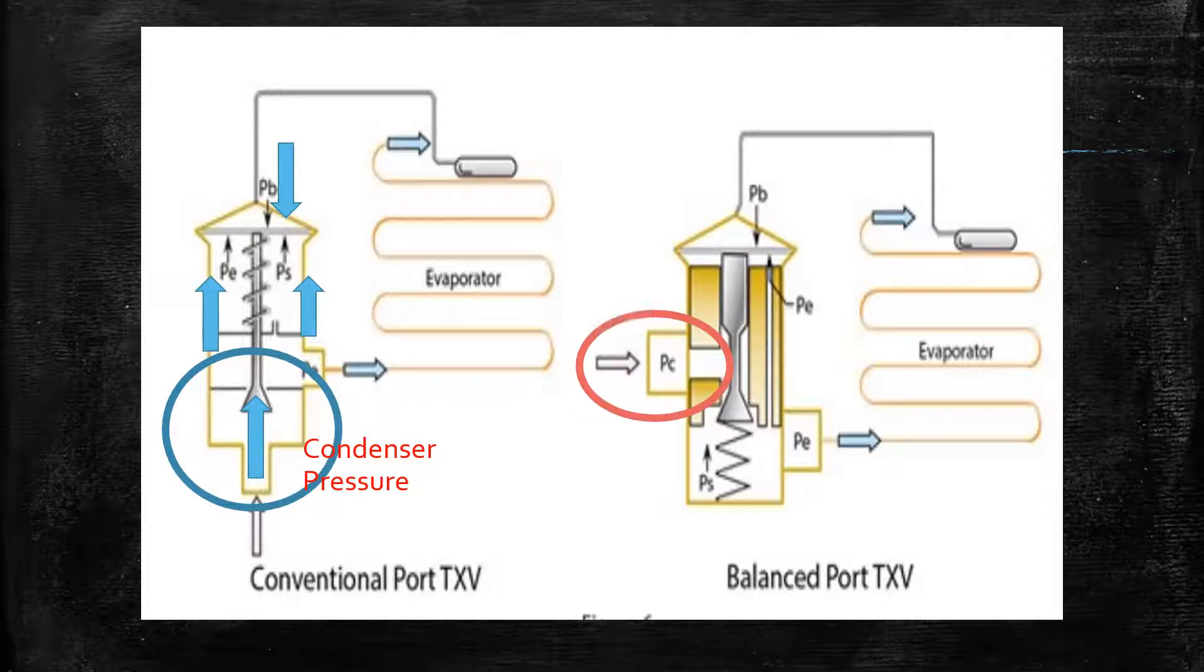On a balanced port TXV, this condenser pressure is isolated from the rest of the valve, and therefore works on the needle in a balanced or equal pressure, not causing any additional pressure on the needle valve to open or close.